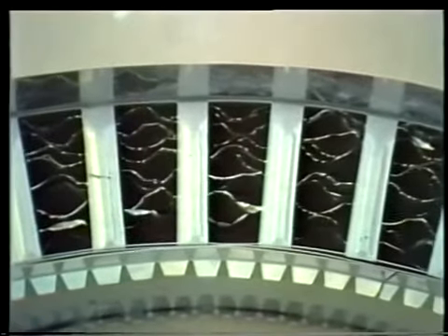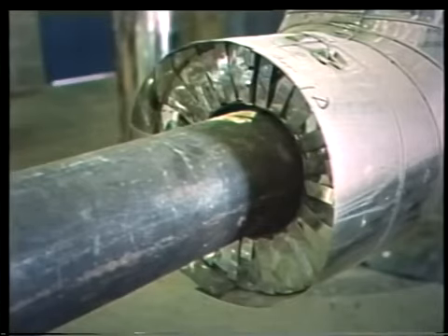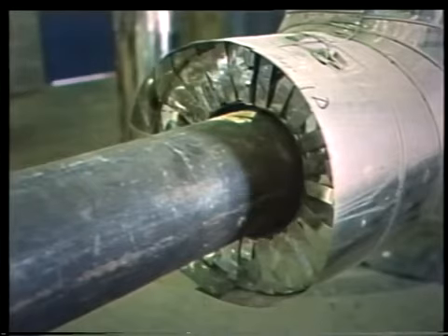Here's an example of many layers of metal foil being used to prevent heat losses. The space between the layers adds insulation value to the piece. Dead air helps keep the heat in. This piece uses mass-type insulation along with reflective foil and sheet metal. The mass-type insulation is sealed between layers of foil, so dusts and fibers can't escape into the clean area.